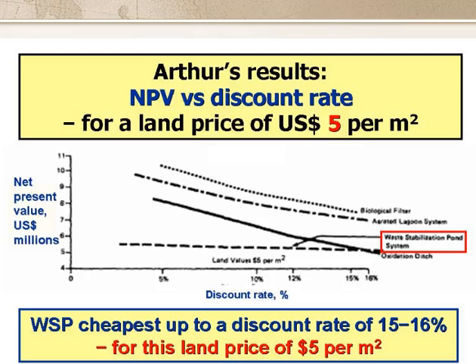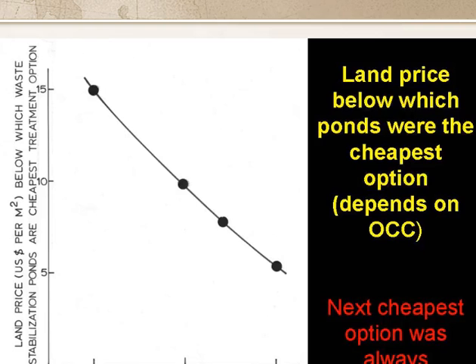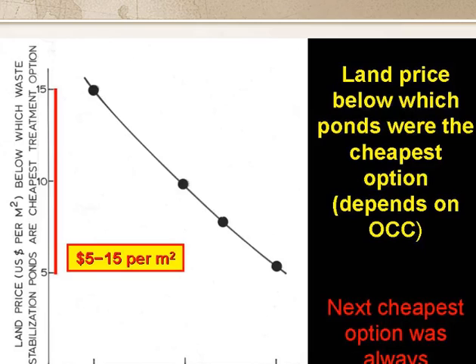He then allowed the discount rate to vary while keeping the land price constant at 5 dollars per square metre. His figure, reproduced in this slide, shows that ponds were cheapest up to a discount rate of somewhere between 15 and 16%; for higher rates, the oxidation ditch was cheapest. He then repeated this for land prices up to 15 dollars per square metre. The y-axis is the land price below which ponds were the cheapest option, and the x-axis is the discount rate — there's almost a linear relationship between these two parameters. This shows the range of land prices between 5 and 15 dollars per square metre below which, depending on the discount rates, ponds were the cheapest option. The next cheapest option was always oxidation ditches.